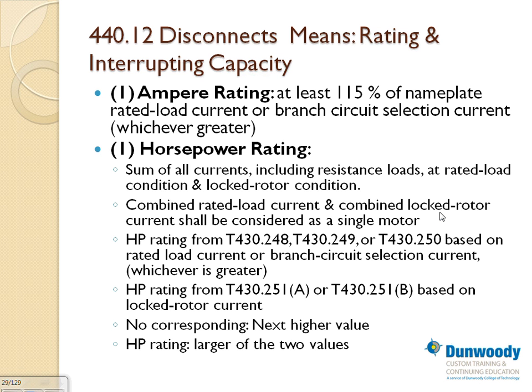Horsepower: you're going to take the sum of all the equipment. The way they do it, guys, they take the locked rotor current of the equipment, the blower and the compressor. If you grab the rotor and lock it and turn the switch on, that's how much current you get. That's the locked rotor current, the starting current, another term for it. Add them all up and go to the tables in the back and size the horsepower based on the locked rotor current and also based on the running current, and choose the largest. If it doesn't correspond to a value, what do you need to do? You go to the higher.